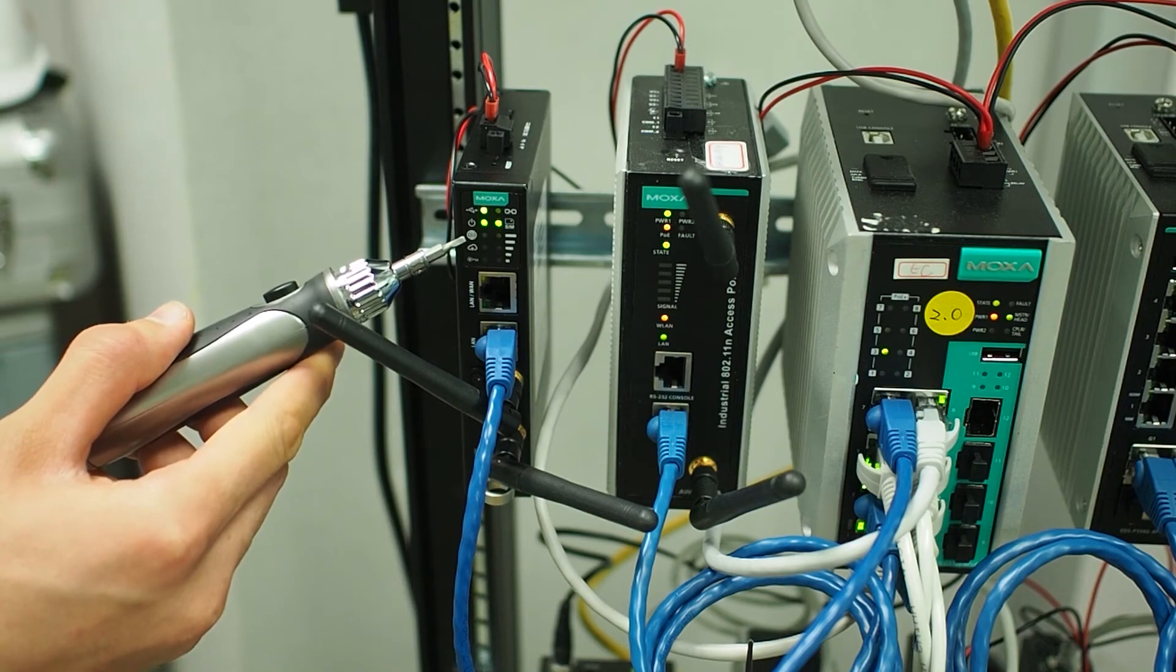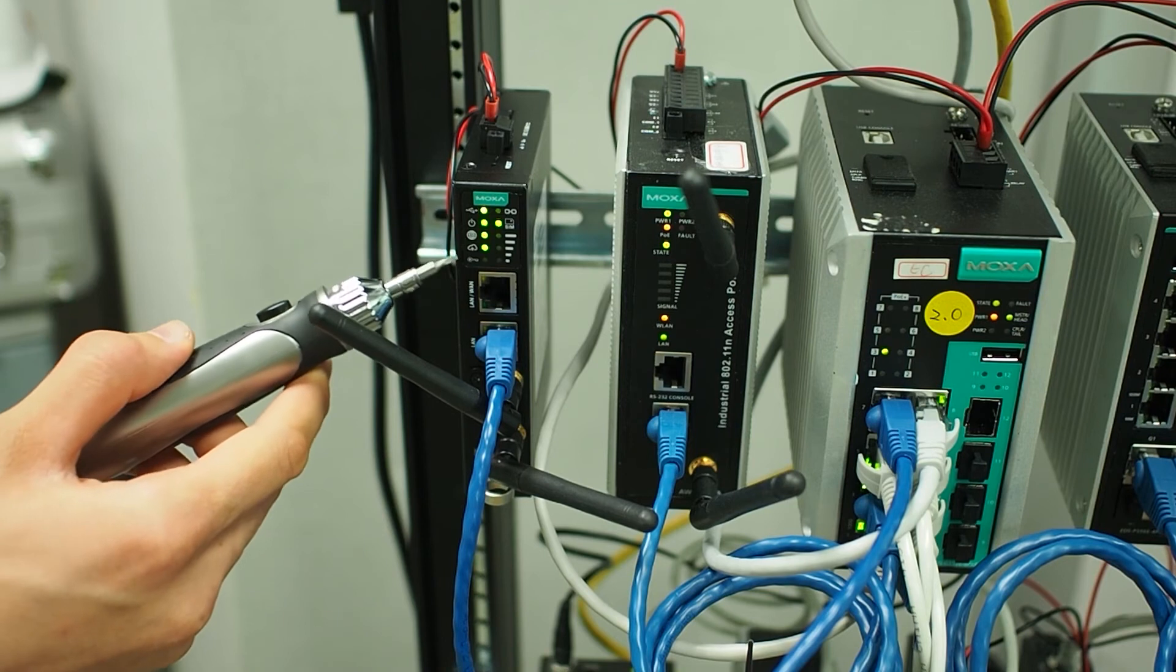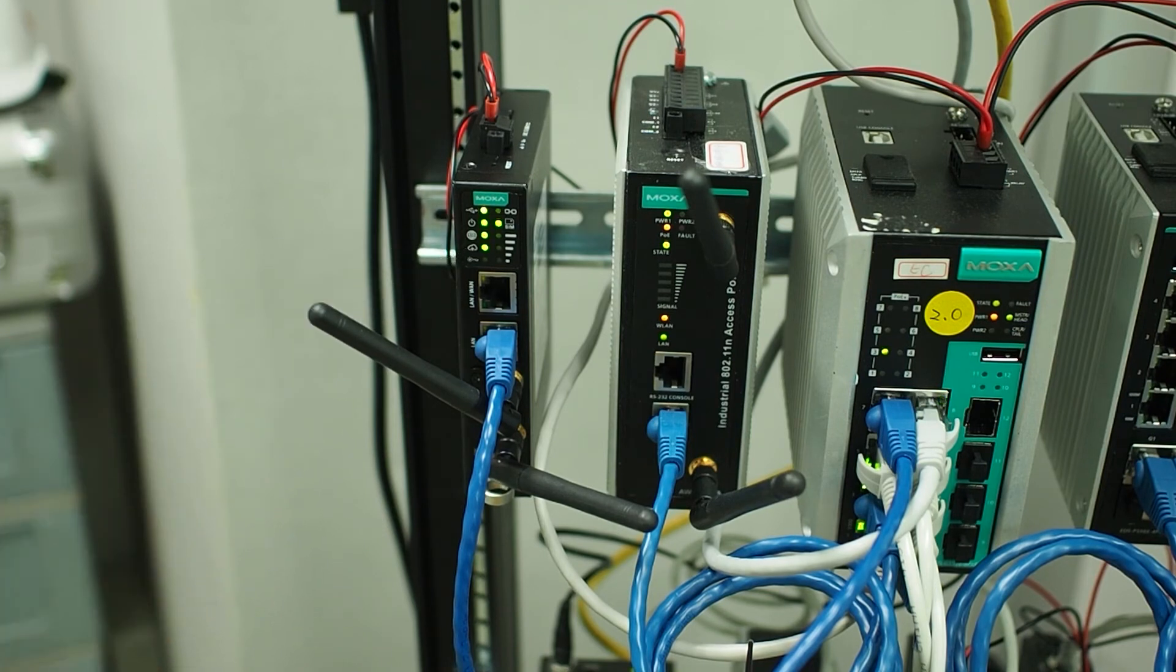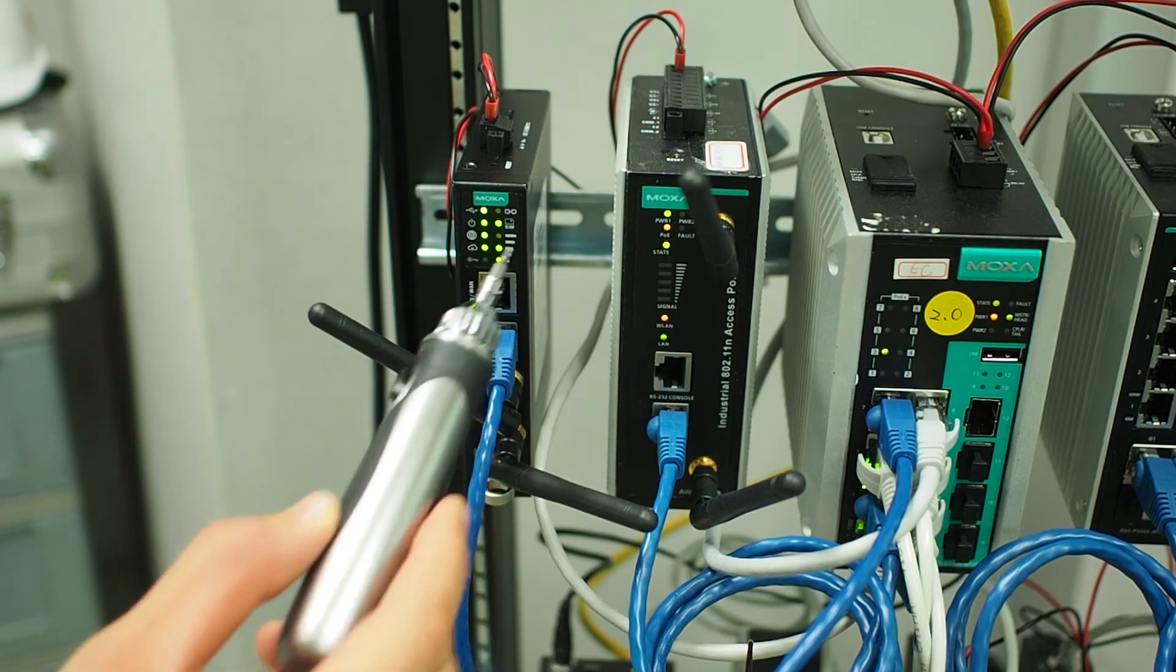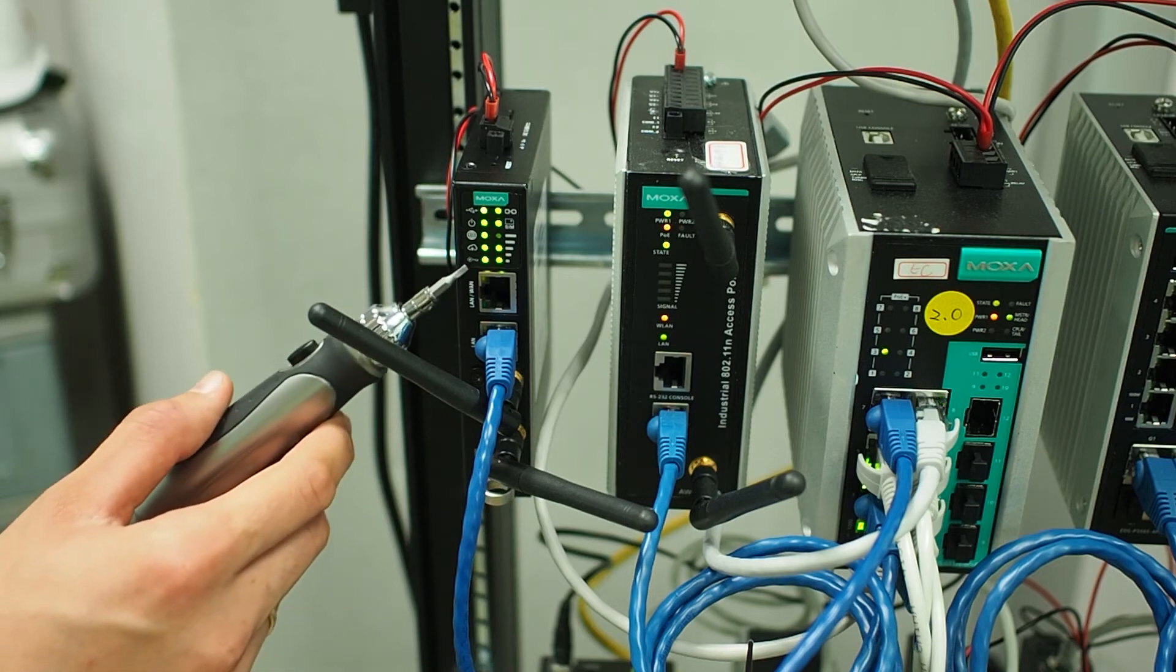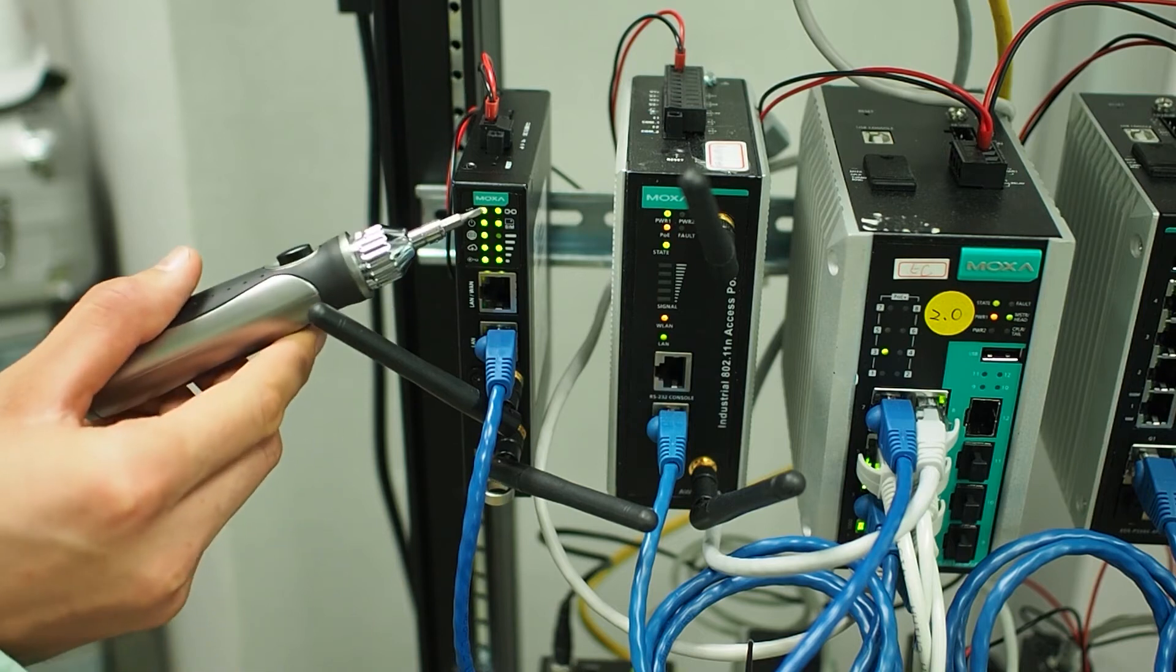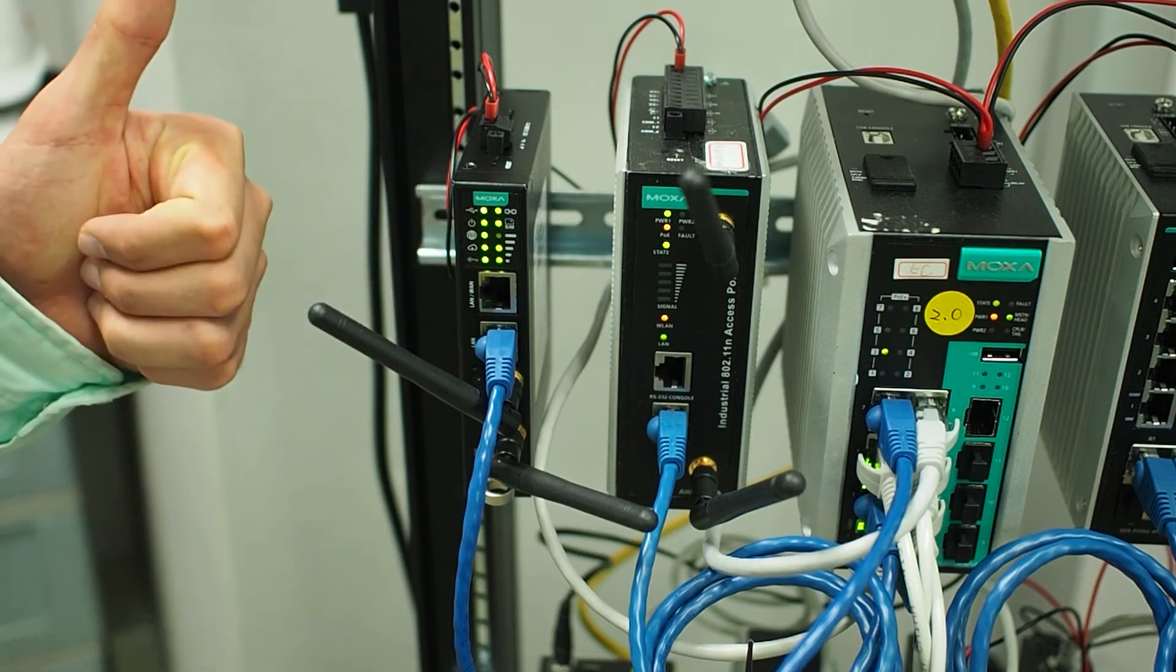And shortly, the cloud LED turns on to indicate connectivity to MRC server. This group of three LEDs on the right is showing cellular signal strength. After a while, you will see last two LEDs turning on, indicating that VPN tunnel is ready. The whole booting process takes about two minutes.